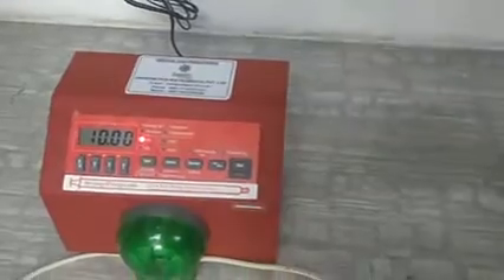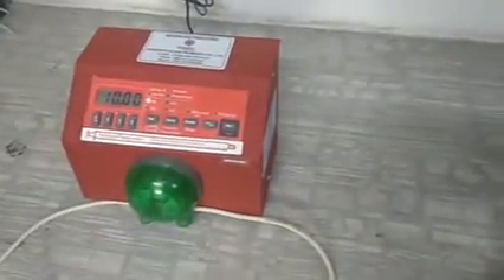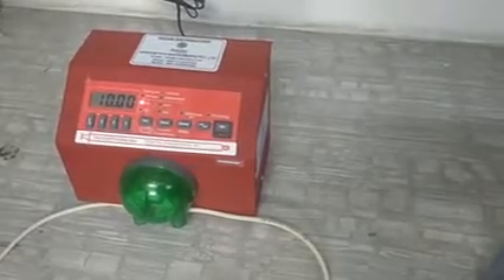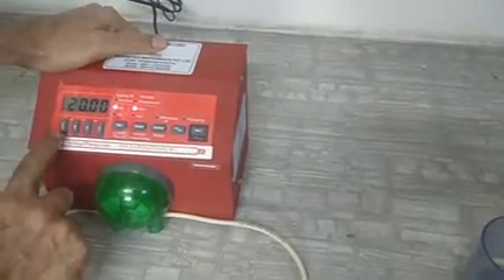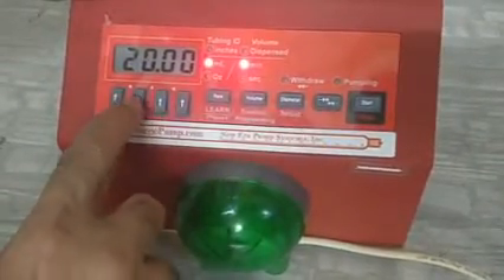On the back end side there is this on off switch. I will make it on. Once you put it on, you will see that 4 digits are flashing. Press any arrow key and it will be stable. If you want to run it for the regular runs, say you have to dispense some volume, suppose we want to dispense 10 ml with a flow rate of 20 ml per minute. So I will make the flow 20 ml per minute. If I have to change it, there are 4 arrow keys, and each arrow corresponds to a digit. Suppose I want a flow of 25, so I can make it 25.